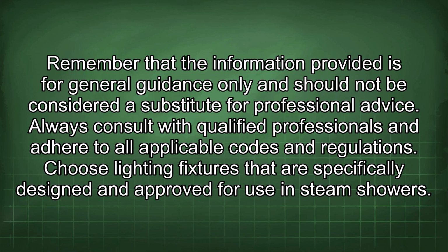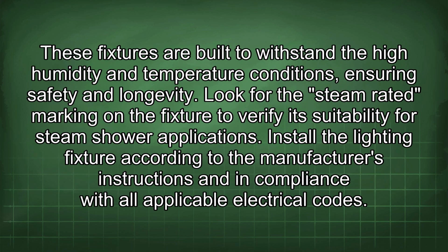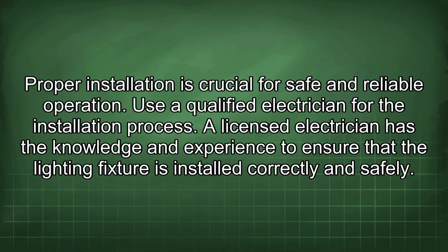Choose lighting fixtures that are specifically designed and approved for use in steam showers. These fixtures are built to withstand the high humidity and temperature conditions, ensuring safety and longevity. Look for the steam-rated marking on the fixture to verify its suitability for steam shower applications. Install the lighting fixture according to the manufacturer's instructions and in compliance with all applicable electrical codes. Proper installation is crucial for safe and reliable operation. Use a qualified electrician for the installation process. A licensed electrician has the knowledge and experience to ensure that the lighting fixture is installed correctly and safely.